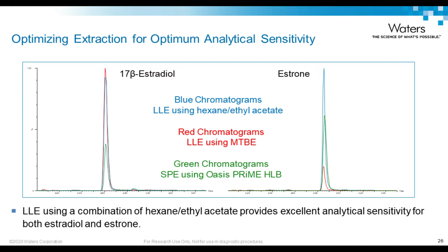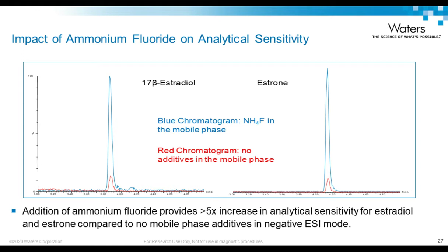The addition of ammonium fluoride as an additive makes a significant difference in analytical sensitivity for the estrogens. Compared to mobile phase with no additives, shown in red, there is a greater than 5-fold increase in analytical sensitivity in electrospray ionization negative ion mode for both estradiol and estrone.